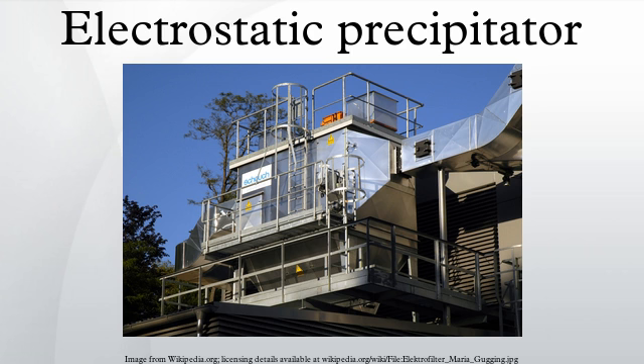A two-stage design has the benefit of minimizing ozone production, which would adversely affect the health of personnel working in enclosed spaces. For shipboard engine rooms where gearboxes generate an oil mist, two-stage ESPs are used to clean the air, improving the operating environment and preventing buildup of flammable oil fog accumulations. Collected oil is returned to the gear lubricating system.